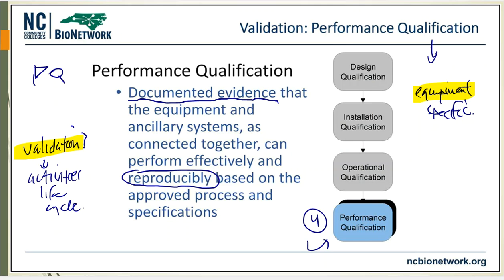We know it works. Someone has done it before multiple times and it's always worked out. So it should work out for you too when you do it. The chromatography instrument, though, that instrument is going to be qualified, not validated. You have validated the process, but the equipment that's used in that is going to be qualified. So we have qualified it to do the job just like you have been qualified to do the job when you were hired with HR.